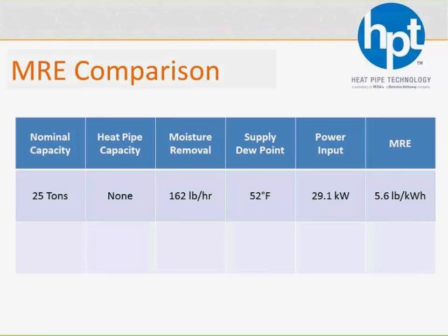Now, we were able to not just use a 25-ton unit, but use a 20-ton unit where we're doing 5 tons of pre-cooling to get you a net 25-ton system, still getting down to the 52-degree dew point, which is therefore going to have the same moisture removal capacity of 162. But again, we were doing ours with less power, because it takes a lot less power to overcome our little bit of static than it does for that 25-ton system to have 5 extra tons of compressor horsepower doing the same work.